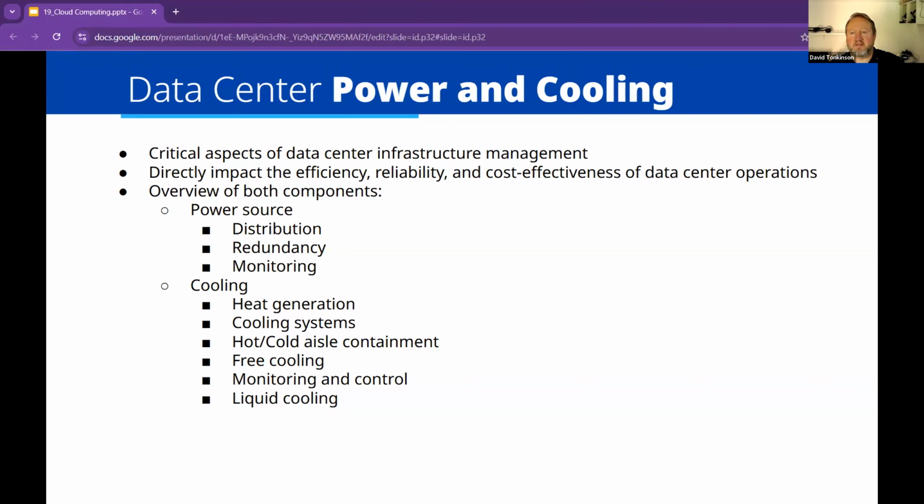Now, did we do stuff on redundancy? Oh, there's a good question. Redundancy for power units is normally considered to be our diesel generators and backup generators and things like that. And we talked about N and N+1. So N is actually the number of generators that I would need to run my data center if I lost all power. So if I have a data center that requires 5 diesel generators to produce enough electricity to keep me running, then I have a 5 diesel generator system.